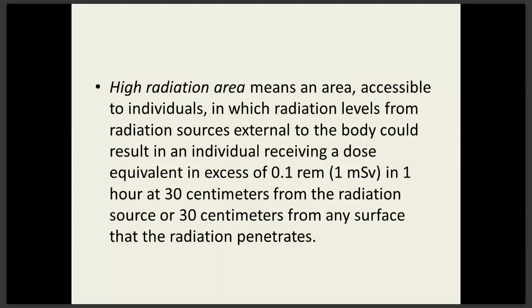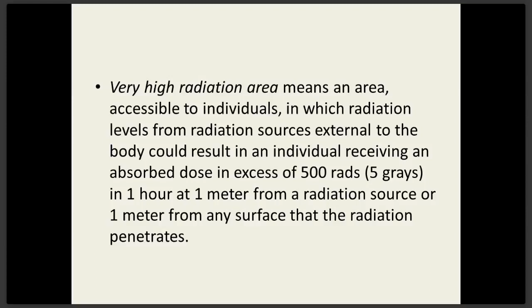So there's three different definitions I want to go over, and one of it depends upon the level of the intensity of the radiation. One is called a radiation area. Radiation area is accessible to individuals if that person can receive 0.005 rem or 5 millirem in 1 hour at 30 centimeters. That is considered a radiation area. A high radiation area is if an individual can receive in excess of 0.1 rem or 100 millirem in 1 hour at 30 centimeters. That is a high radiation area. And the areas that we work in, linear accelerator vaults, are considered very high radiation areas because someone in that vault can easily get in excess of 500 centigray in an hour at a meter. So vaults are always considered high radiation areas.